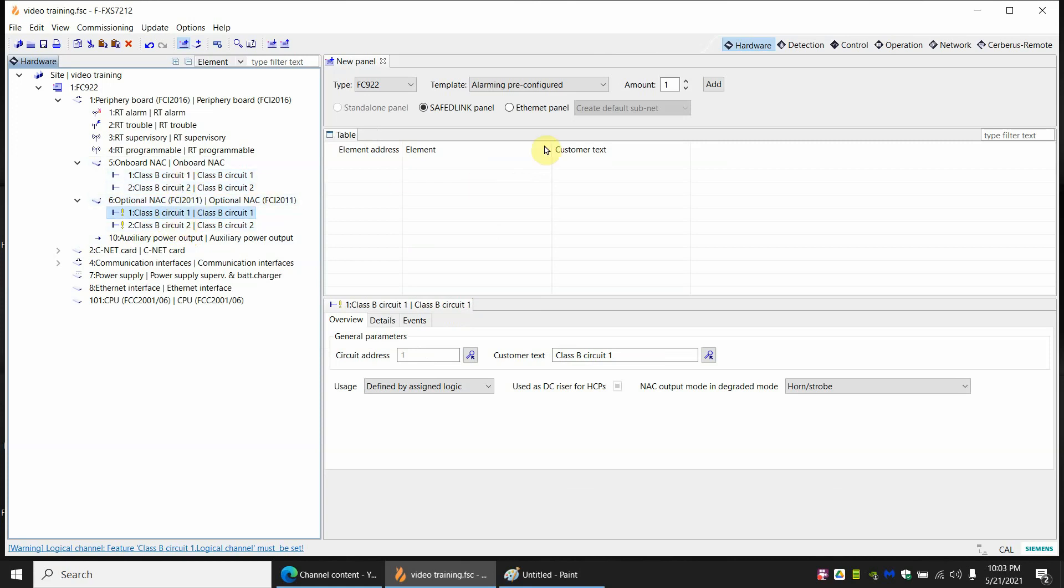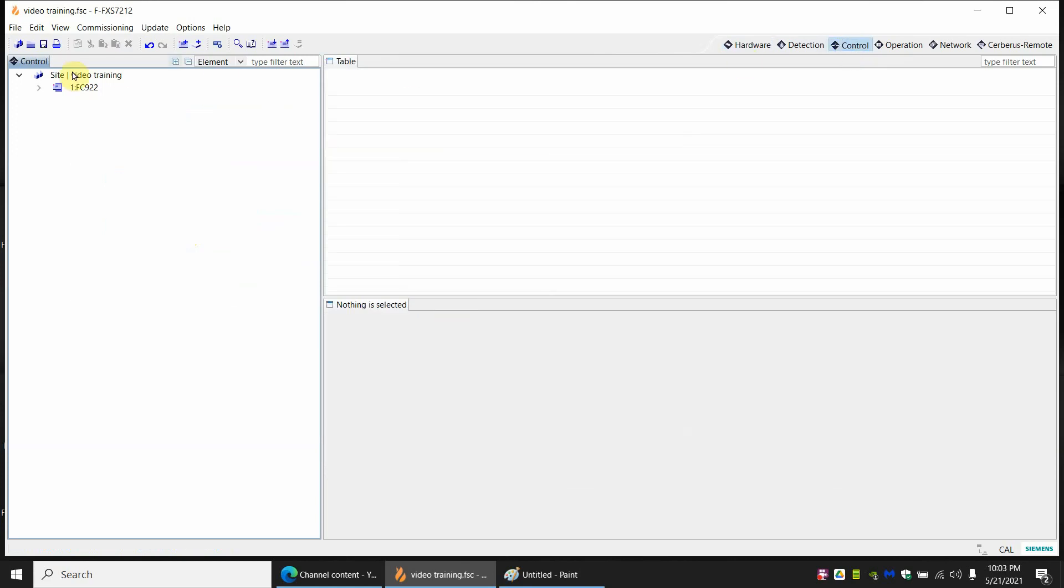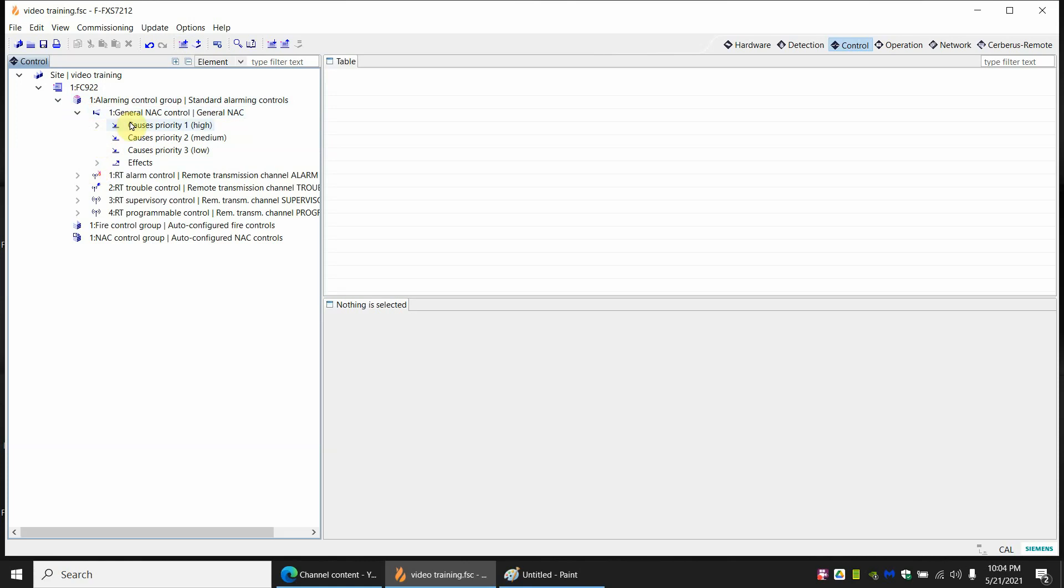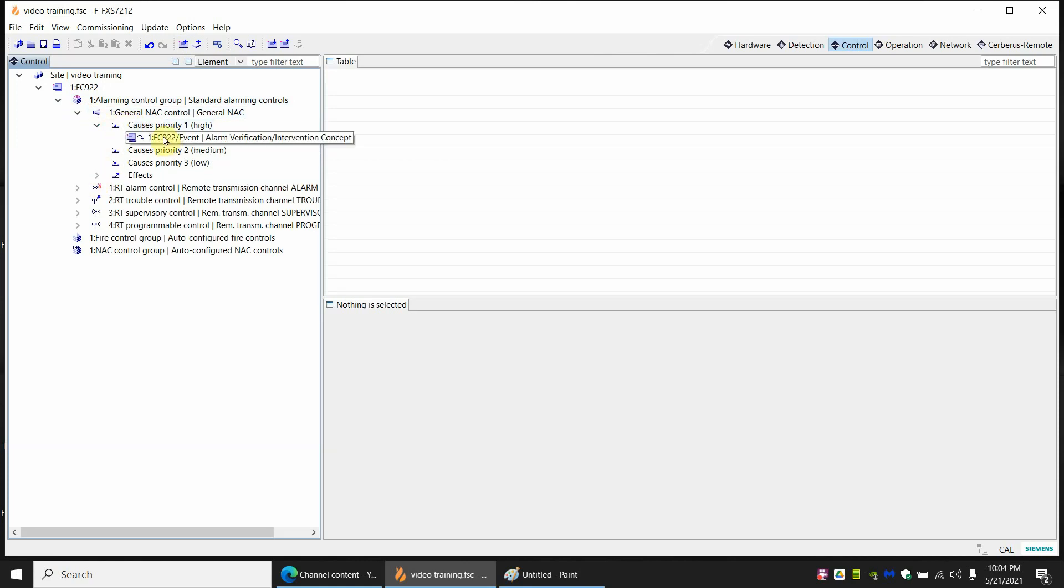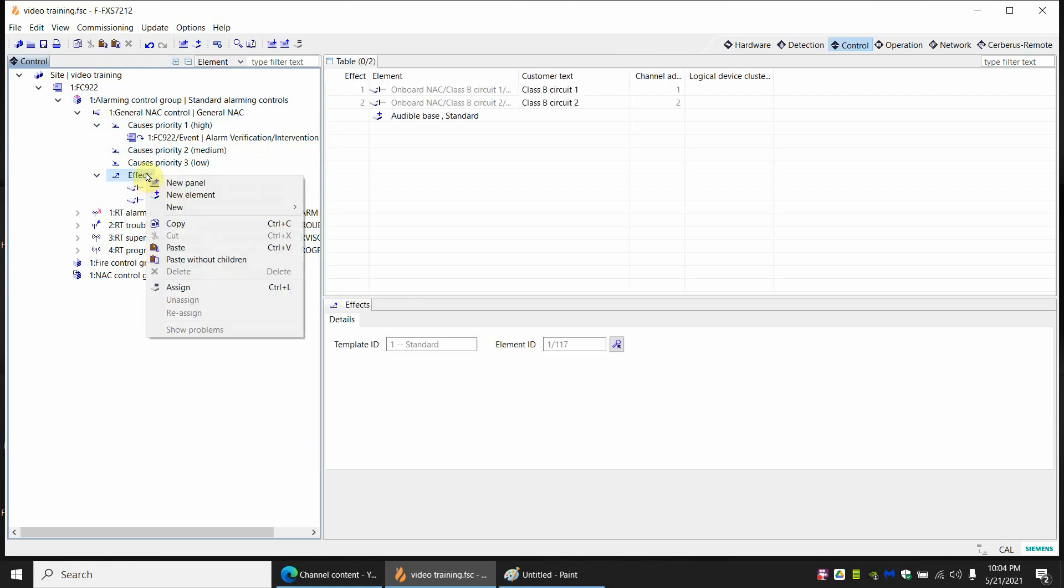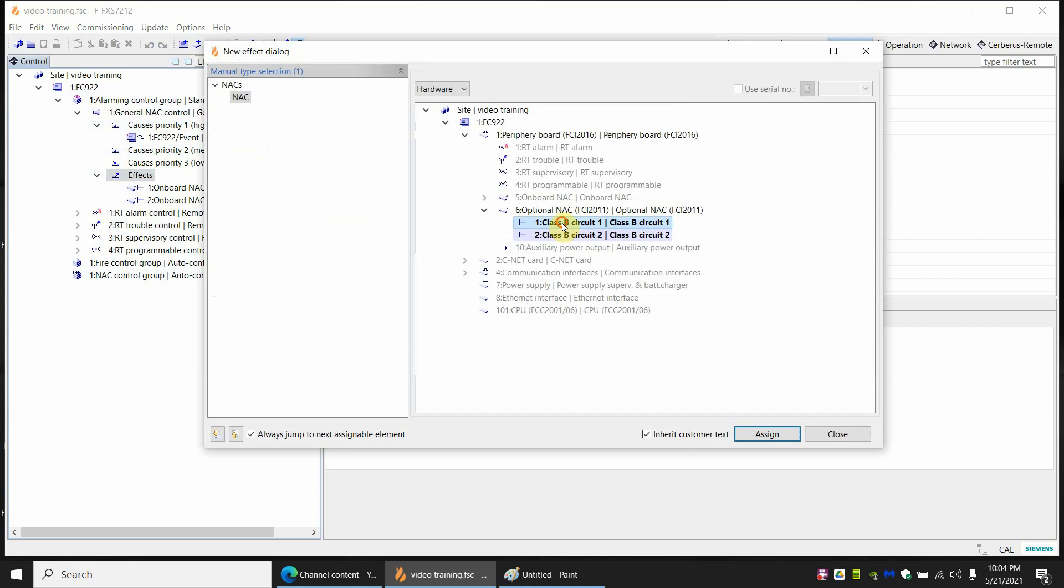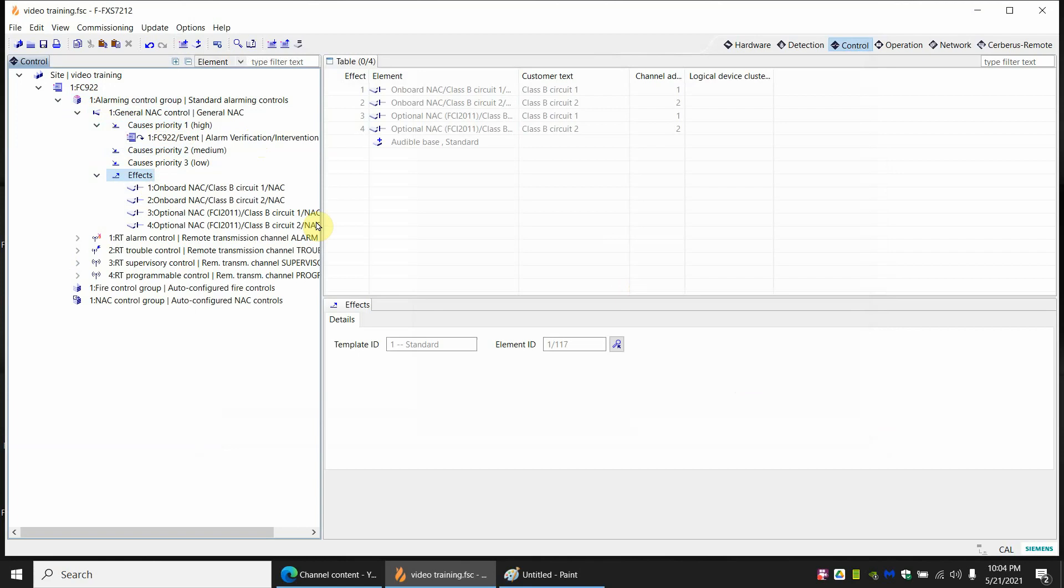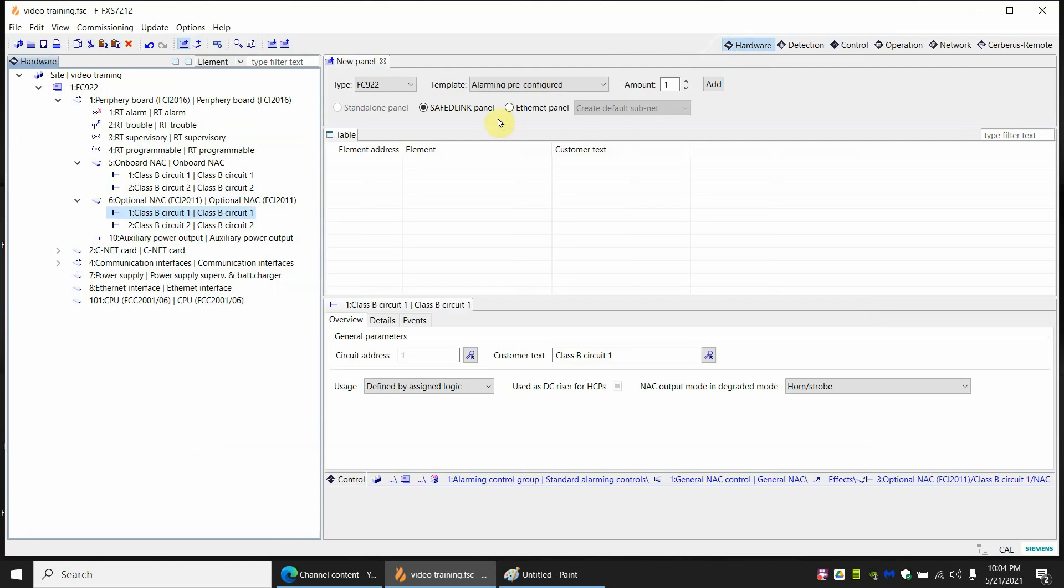To make that work we're going to go to the control tab. If you open up by default it adds an automatic or alarming control group. Let's open that up and you see it adds one for general NAC control. And the cause on here if you open it up would be an alarm. The effects it has to two NACs. We want to add two more NACs. So we will click on effects and we will right click and assign. We're going to add these two NACs. You can add one at a time or click them both and hit assign. And close the window. Now if we have an alarm all four NACs should go off. And with that the NAC should be totally functional.